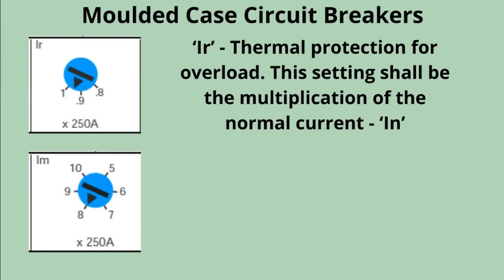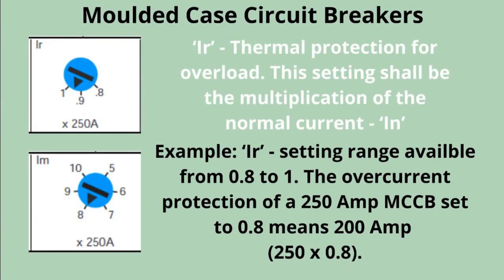IR is the thermal protection setting for overload. This shall be a multiplication of the normal current. For example, the IR setting range is available from 0.8 to 1. The overcurrent protection of a 250 amp MCCB set to 0.8 means 200 amp — that is 250 multiplied by 0.8.